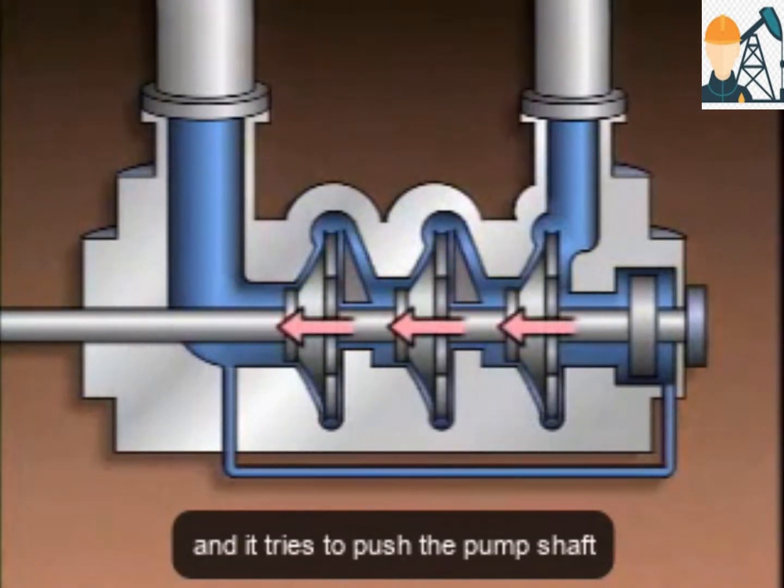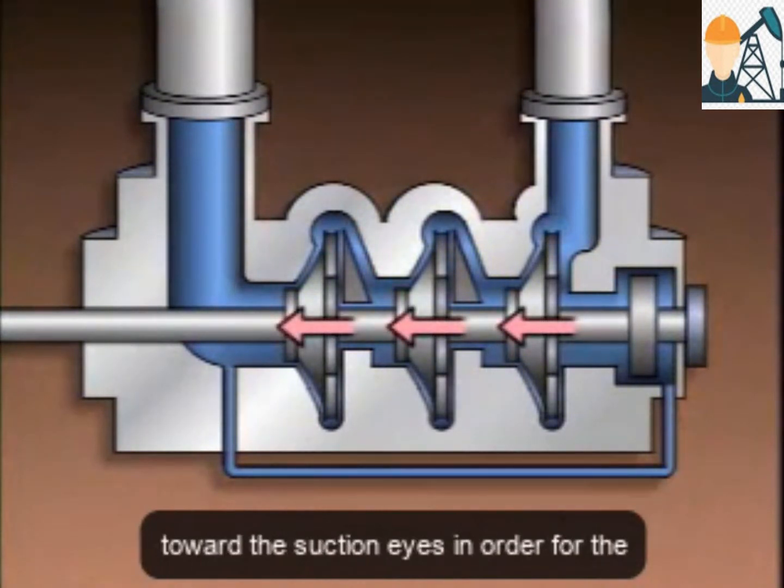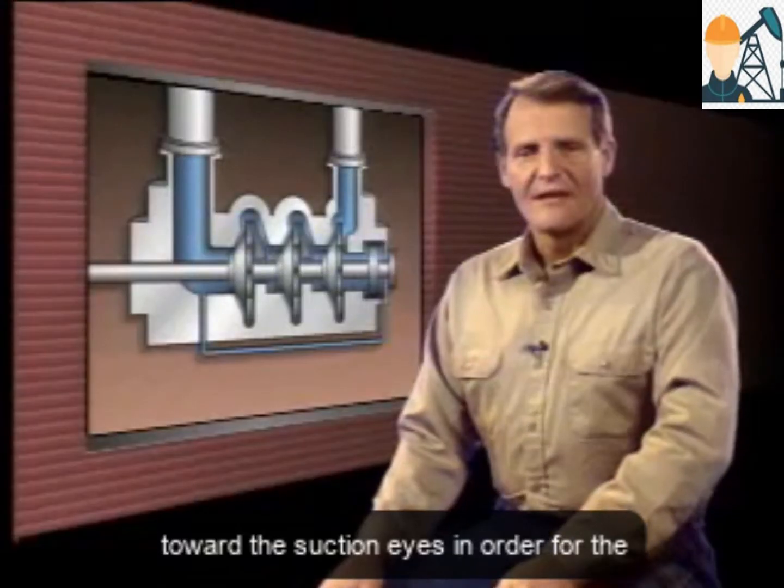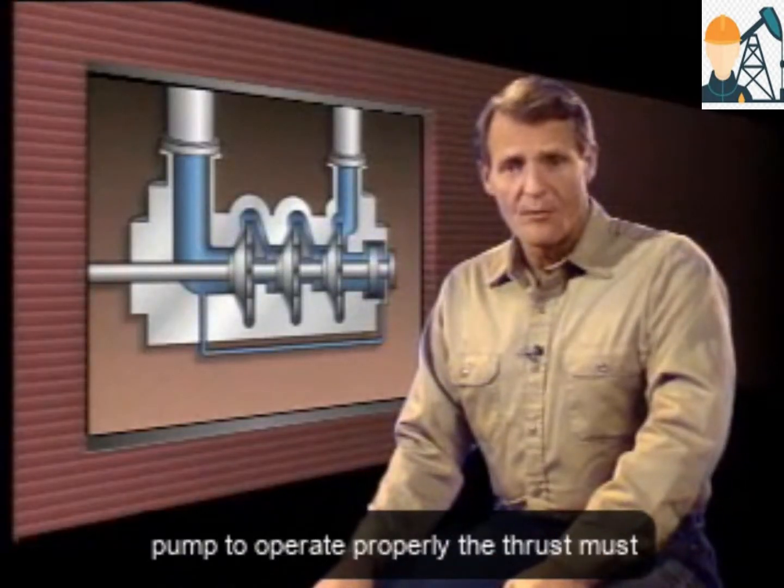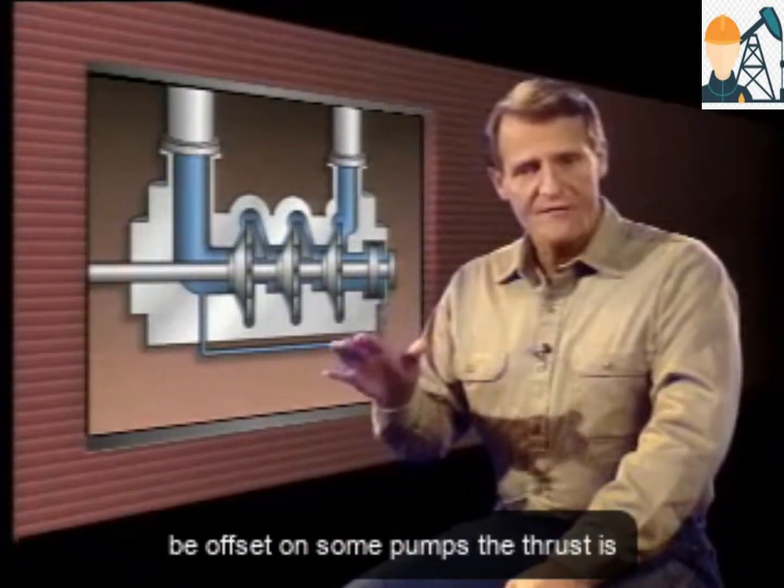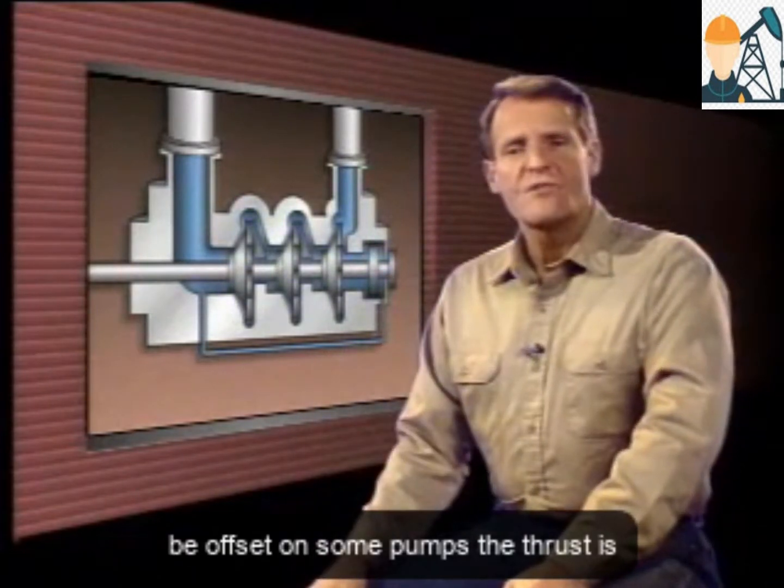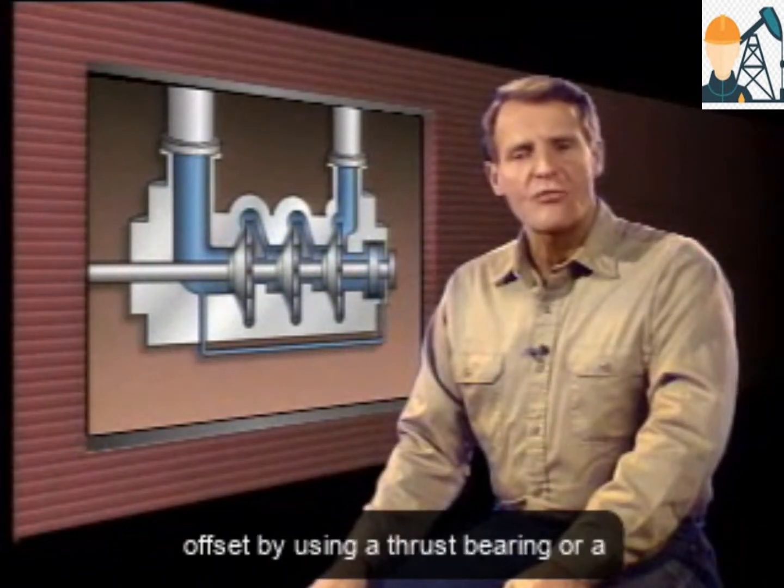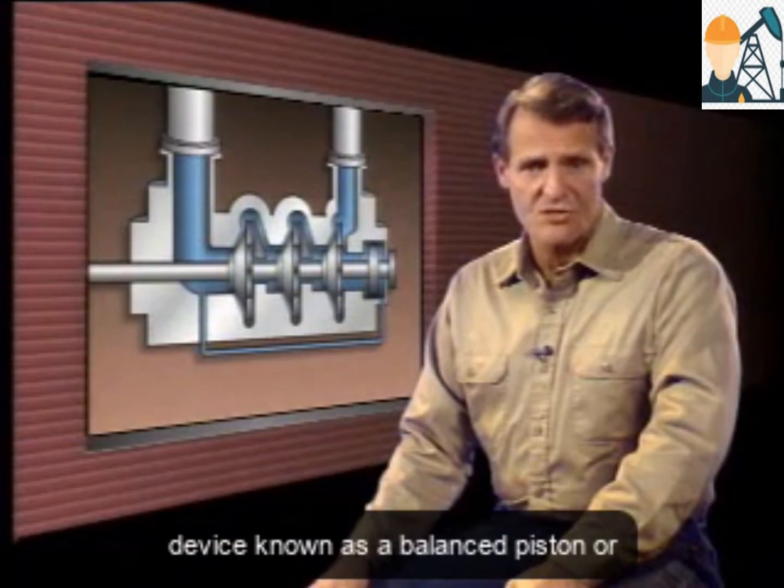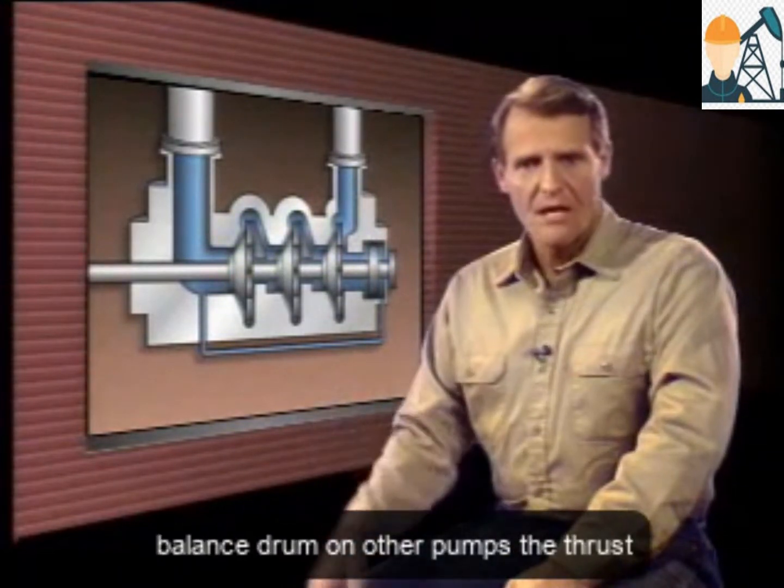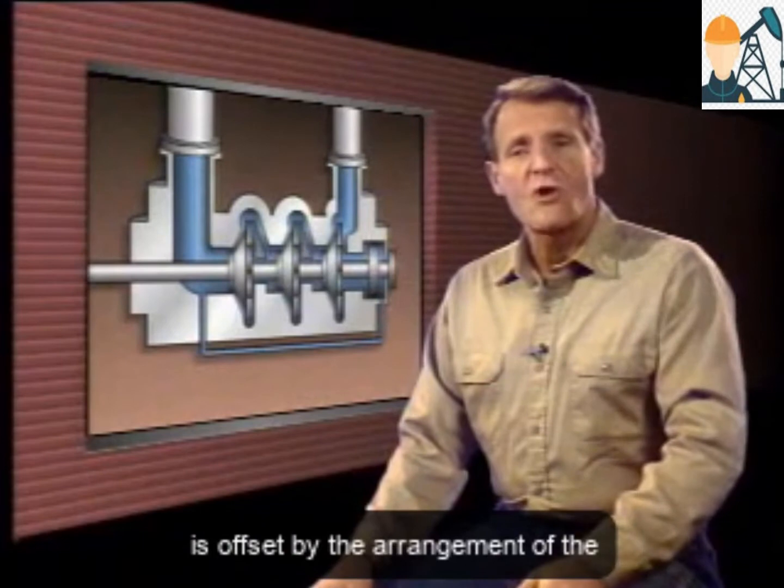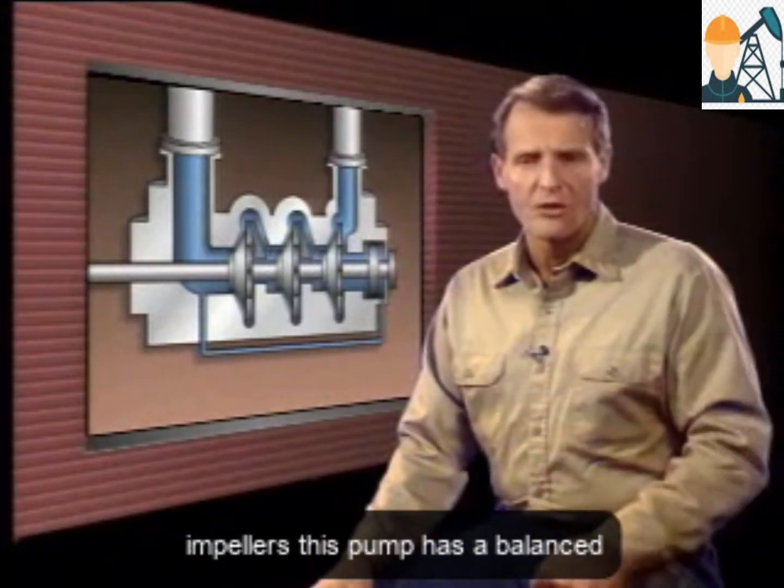And, it tries to push the pump shaft toward the suction eyes. In order for the pump to operate properly, the thrust must be offset. On some pumps, the thrust is offset by using a thrust bearing or a device known as a balance piston or balance drum. On other pumps, the thrust is offset by the arrangement of the impellers.